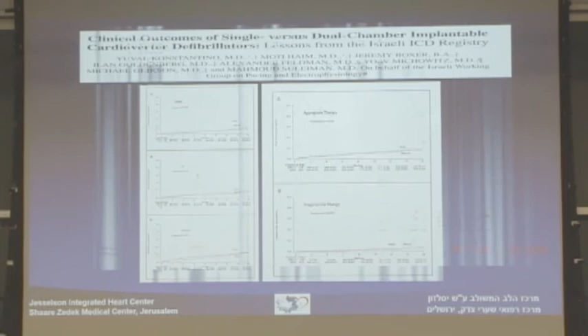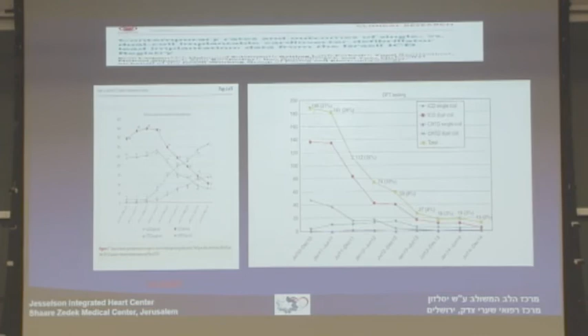The issue of single versus dual coil is also an evolving issue over the years. Until not so many years ago, we used to implant mostly dual coil ICDs because we believed that the DFT was better with dual coil ICDs, whereas as we became more acquainted with extraction, we realized that dual coil is much more difficult to extract, and people tended to move to single coil devices, single coil leads and single coil devices. And what you see here is a tendency over time, based on our registry of implantation.